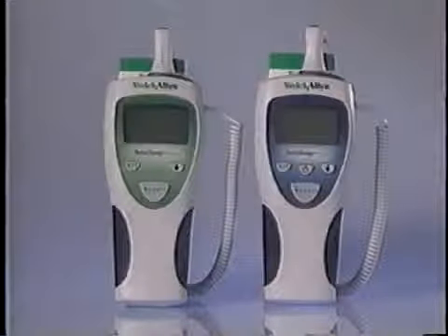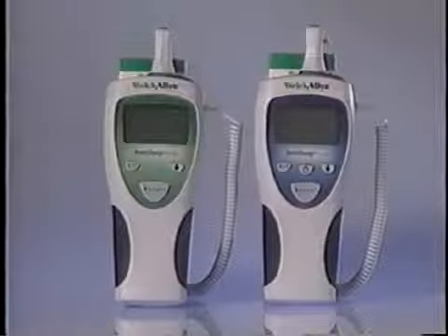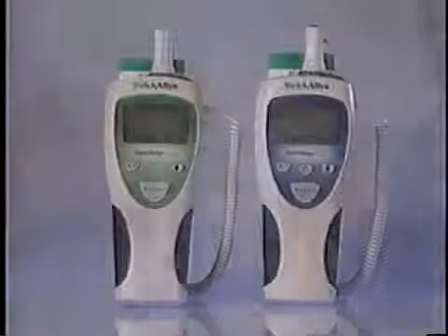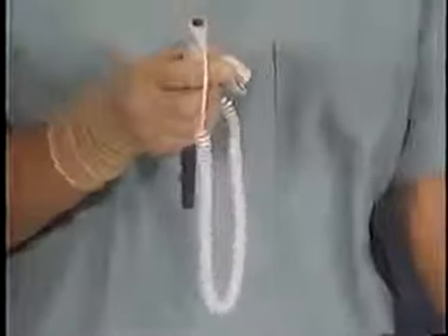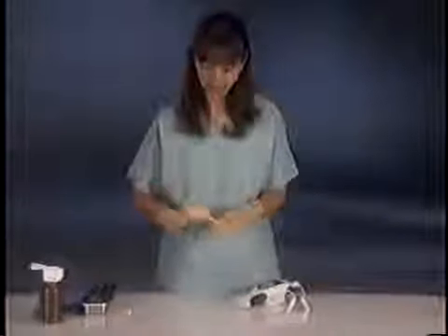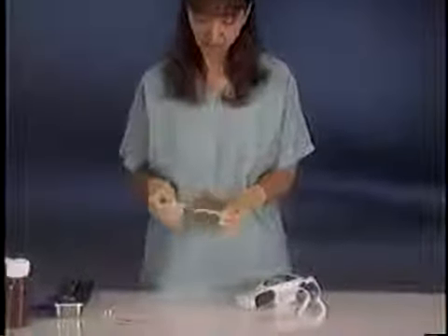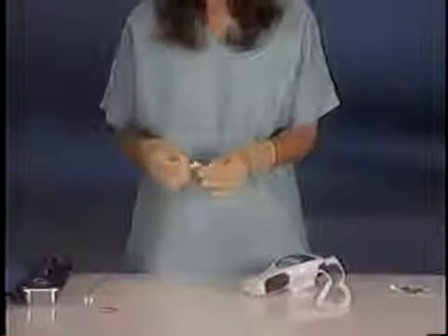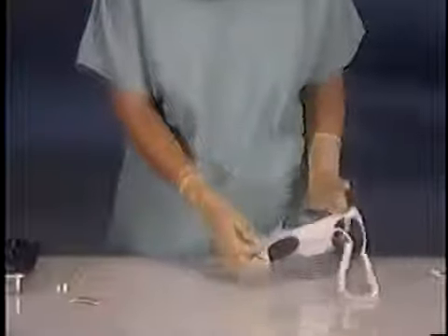Your SureTemp Plus will provide years of trouble-free service with minimal regular maintenance. Clean the probe well on a regular basis, being sure to remove it from the thermometer for cleaning. Swab the inner surface of the well with a solution approved by your facility. Do not use hard or sharp objects. Disinfect the thermometer, probe, and probe well with isopropyl alcohol, 10% bleach, or other solution approved by your hospital according to your facility's policy, or whenever contamination occurs.